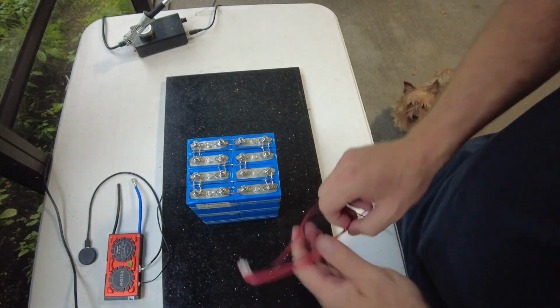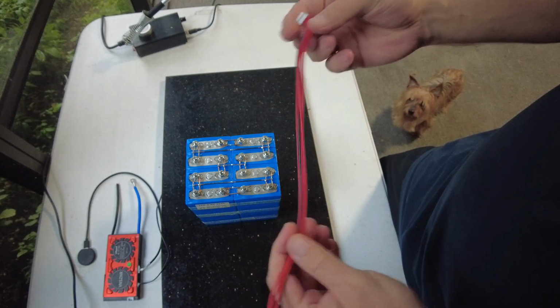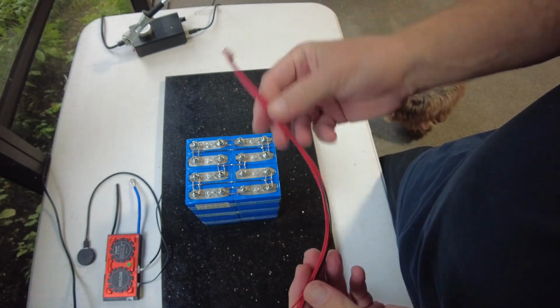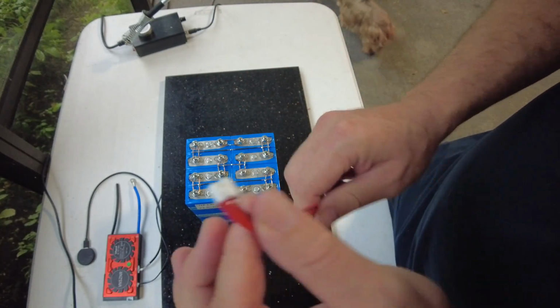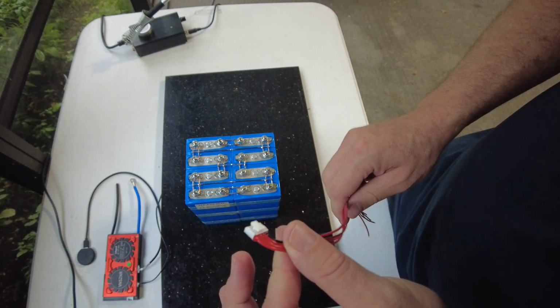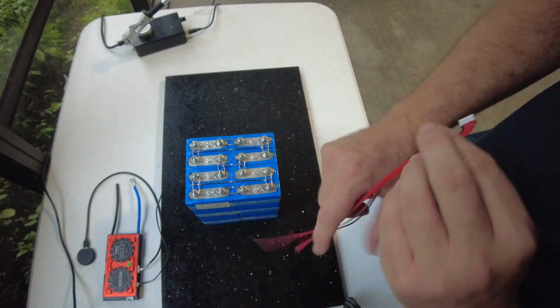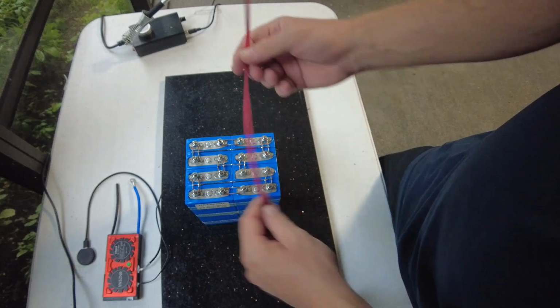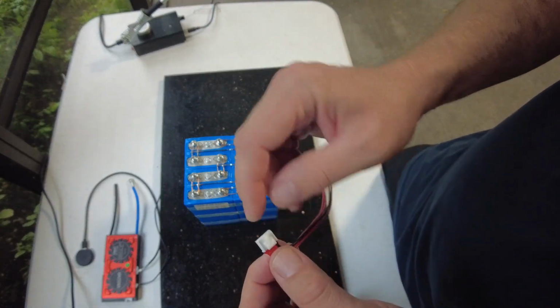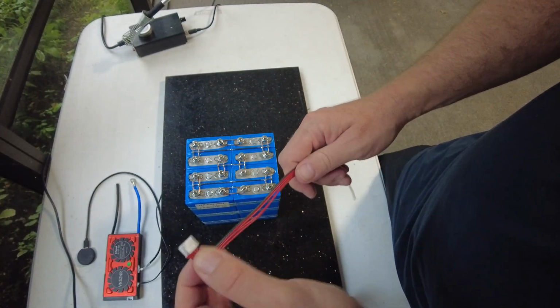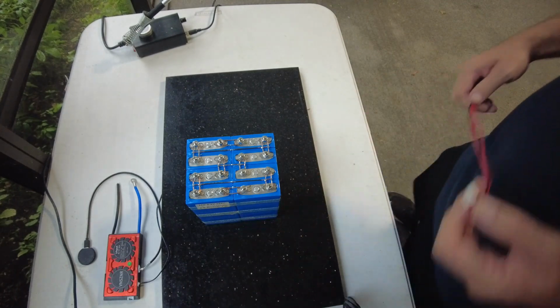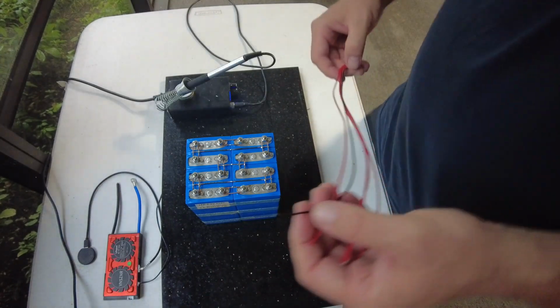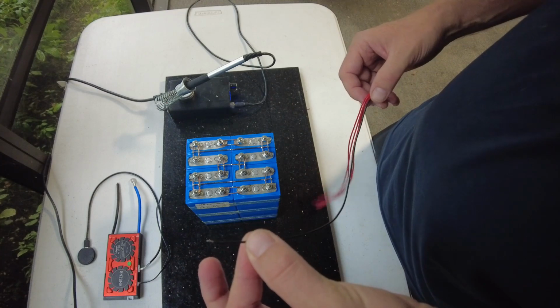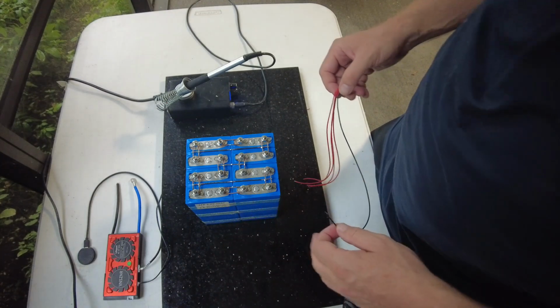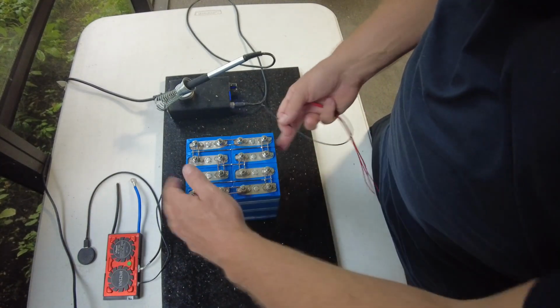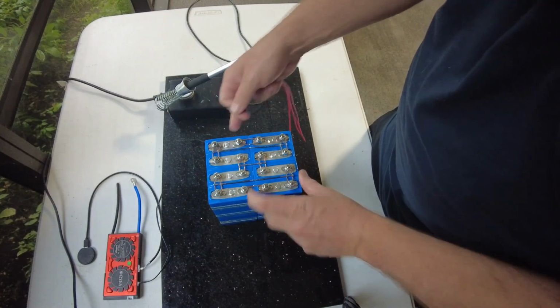And that's what I'm going to do now. When you connect the BMS sense leads, you do it with the sense wire disconnected from the BMS. That way you don't get something shorted out, and after it's all done, we can test to make sure everything's connected properly before we plug it into the BMS. The black wire will go to your most negative, which is actually this one. So that's where we'll start.